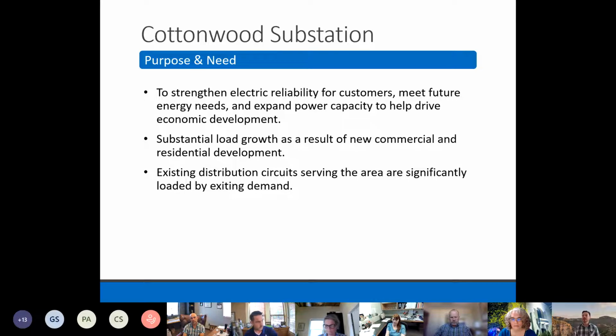The purpose and need of the substation is to strengthen electric reliability for customers, meet future energy needs, and expand power capacity to help drive economic development in the surrounding area. The area west of I-19 from Star Pass Boulevard to Irvington Road has seen substantial load growth from new commercial and residential developments. Currently, this area is served by 5 distribution circuits from 3 separate substations. An analysis of this existing infrastructure has determined that each of the distribution circuits is significantly loaded by the existing demand. In order to provide contingency support and allow for greater flexibility in response to outages, construction of a new substation is necessary.